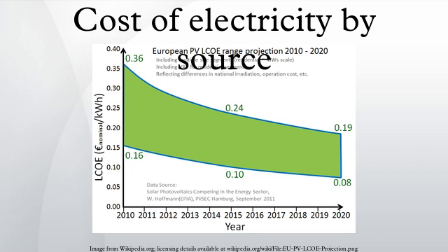From the EIA report, levelized cost represents the per kilowatt-hour cost of building and operating a generating plant over an assumed financial life and duty cycle. Key inputs to calculating levelized costs include overnight capital costs, fuel costs, fixed and variable operations and maintenance costs, financing costs, and an assumed utilization rate for each plant type. The availability of various incentives, including state or federal tax credits, can also impact the calculation of levelized cost. The values shown in the tables in this discussion do not incorporate any such incentives.